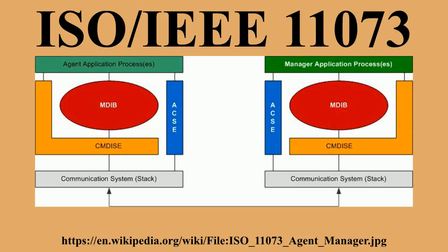In the process, an MDS create event in the form of a report will be triggered. This report creates a copy of the MDS root object from the agent MDIB in the manager MDIB. Afterward, a context scanner object is created in the agent MDIB.